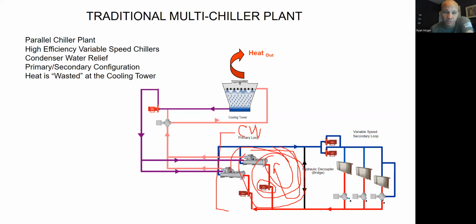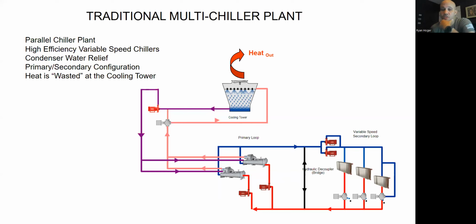That's what they do. And then this loop over here, which is the same water, is the secondary loop. So what those guys do is, as these zones need more water, they turn on one, or in this case, two parallel circulators. That's for redundancy reasons, kind of like the reason you have two chillers instead of one in case one goes down. Two circulators instead of one in case one goes down, or if it's really, really hot, you might run both.